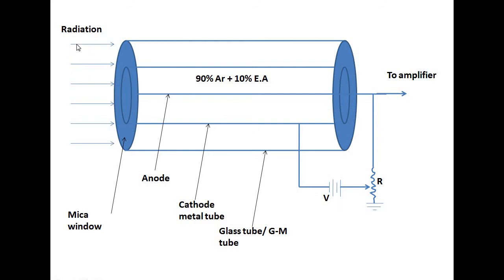When a high energy particle enters into the tube, it ionizes one or more argon gas atoms. The electrons are attracted towards the metal wire or anode, and positive ions are attracted towards the cathode. The moving charges ionize the argon gas, and the ethyl alcohol vapor prevents undesirable avalanching. After ionization, a current pulse passes through the circuit and produces a voltage pulse of between 5 and 50 volts. This pulse is applied to a counter and the number of incoming radiations can be counted.